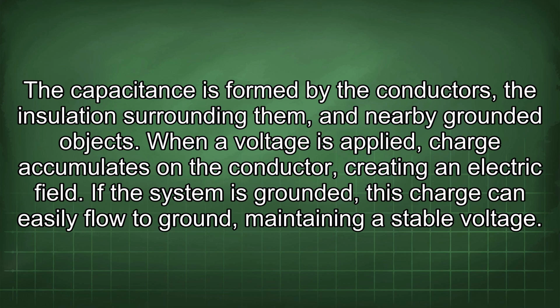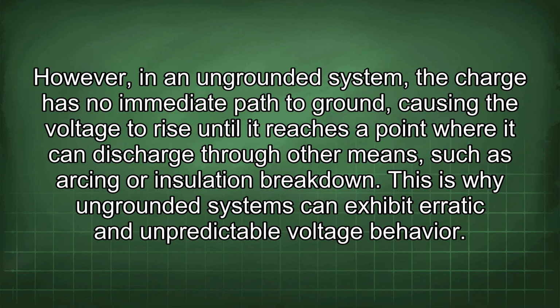If the system is grounded, this charge can easily flow to ground, maintaining a stable voltage. However, in an ungrounded system, the charge has no immediate path to ground, causing the voltage to rise until it reaches a point where it can discharge through other means such as arcing or insulation breakdown. This is why ungrounded systems can exhibit erratic and unpredictable voltage behavior.